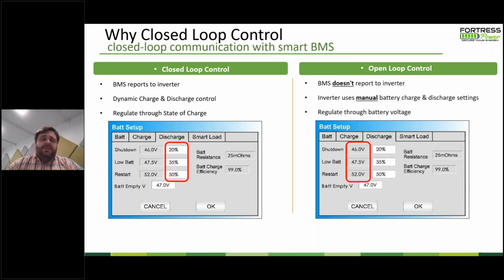The main difference, though, is what the customer wants, not necessarily what the customer needs. Voltage-based controls are very precise for turning off the battery at low states of charge and preventing the battery from overcharging. But what the customer wants with closed loop control is to know what the battery state of charge is as a percentage rather than as a voltage. And so by selecting the closed loop control, the thing is, the battery percentage is very difficult to calculate. The voltage range on these batteries is pretty flat, much more flat than on a lead acid battery. And that's actually a good thing.